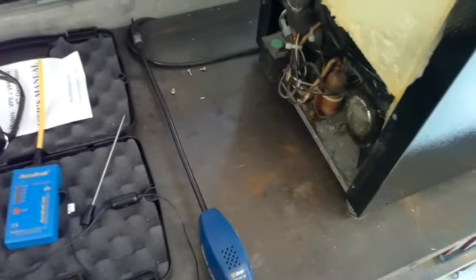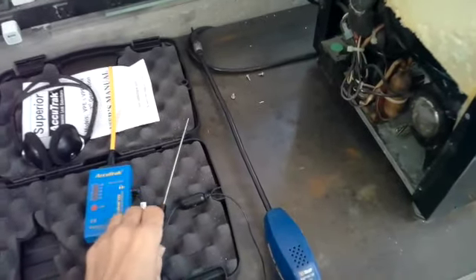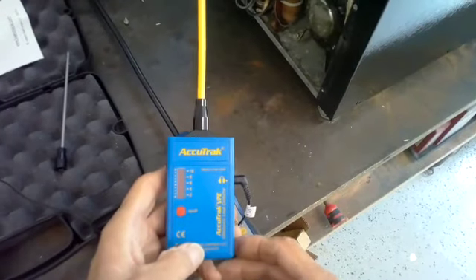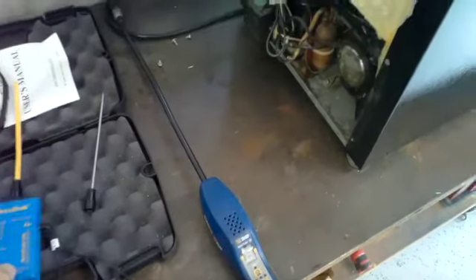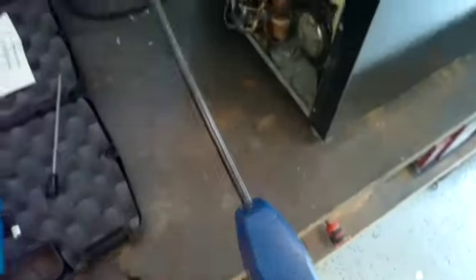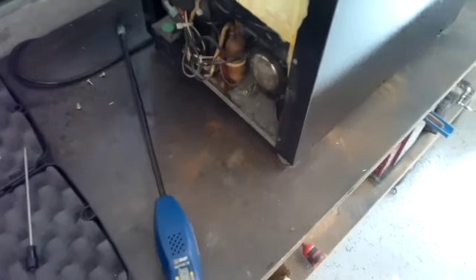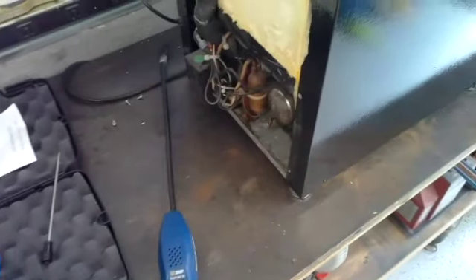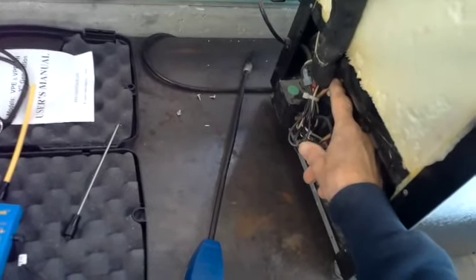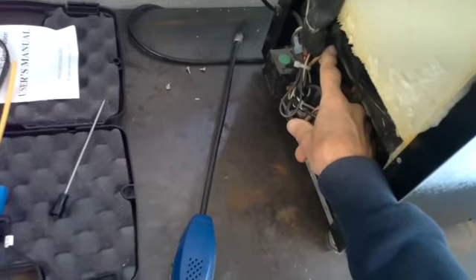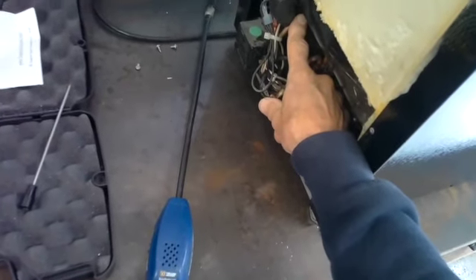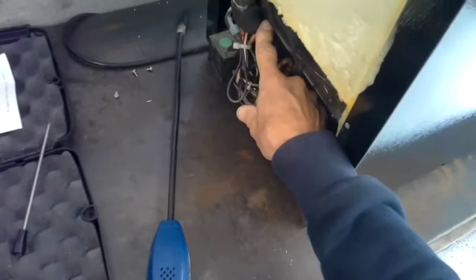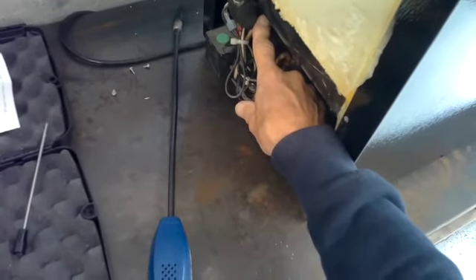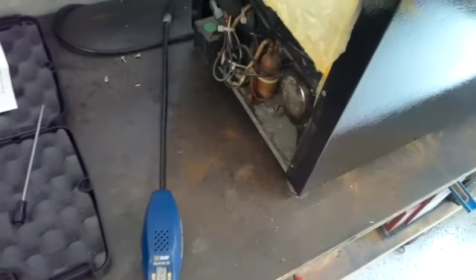Okay, we were not successful in finding any leaks with the ultrasound. So then we used the sniffer, and we can't find any leaks either. So it's either a very slow leak. What we're going to have to do now is put a process port on the low side of the system and drain all the gas out. And then we will pressurize it with nitrogen and try finding the leak that way. So that will be our next step.